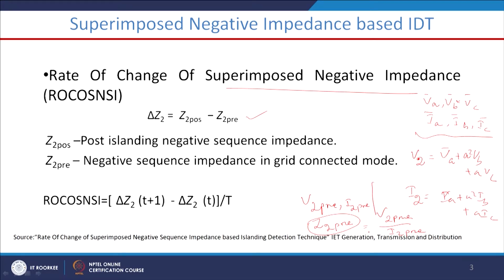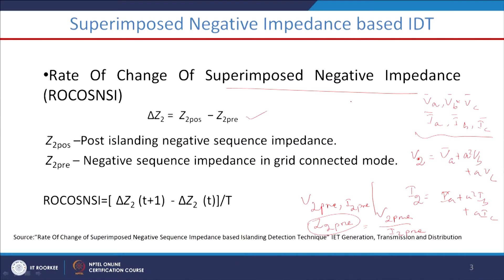Now, suppose islanding occurs. During islanding mode of operation, the islanding relay mounted at the terminal of the DERs continuously measures voltage and current, and the corresponding negative sequence components are calculated continuously. So Z2 is continuously calculated at the terminal of the distributed energy resources. When islanding occurs, V2_post and I2_post are also calculated, and we compute Z2_post = V2_post / I2_post.